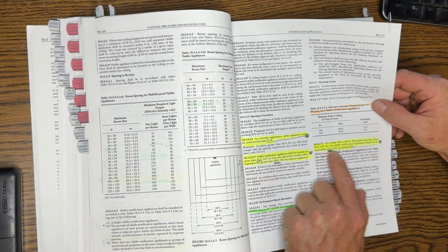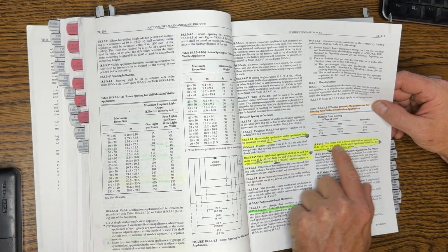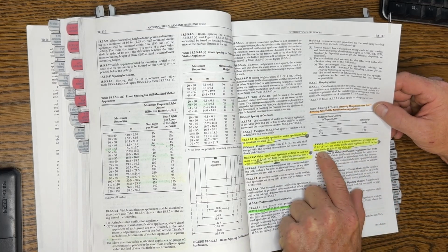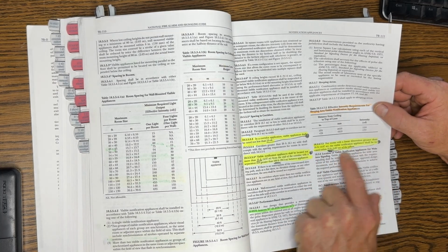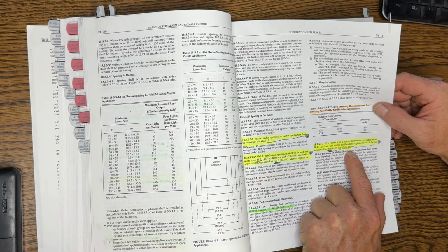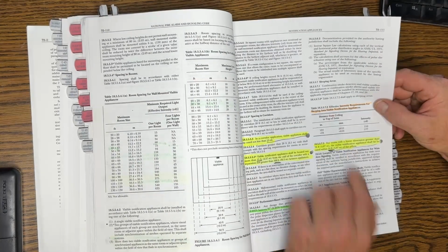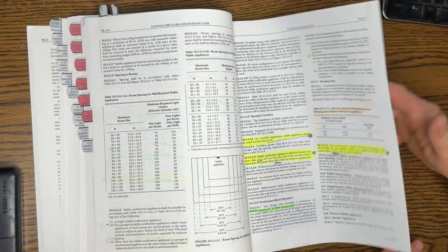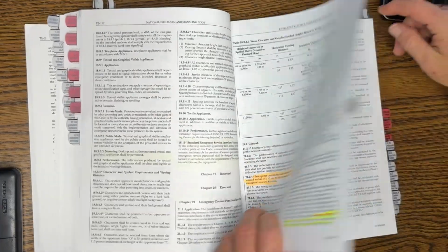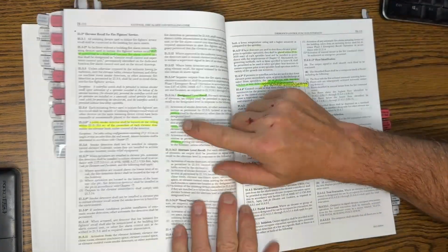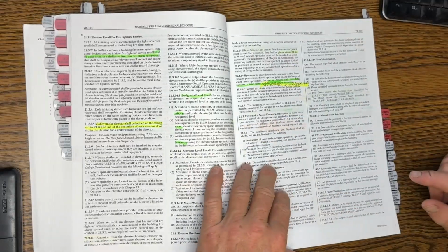Okay, let's see. This was another one. For rooms with a linear dimension greater than 16 feet, the visible notification appliances shall be located within 16 feet of the pillow. So our occupancy, performance space, sleeping areas. There it is. All right, let's see. What else do you have? Lobby.